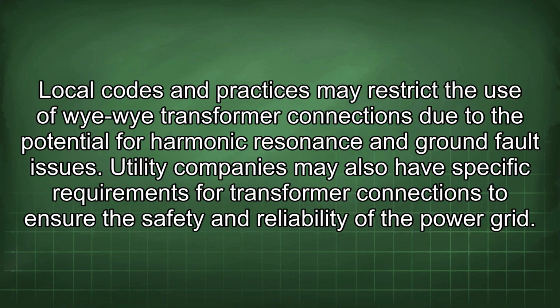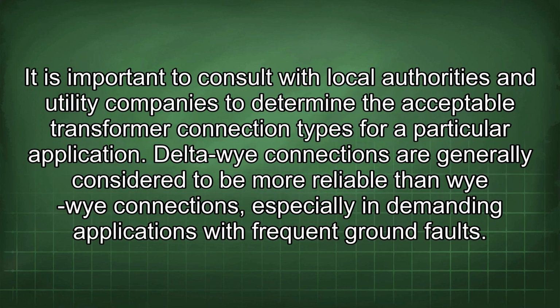Local codes and practices may restrict the use of Wye-Wye transformer connections due to the potential for harmonic resonance and ground fault issues. Utility companies may also have specific requirements for transformer connections to ensure the safety and reliability of the power grid. It is important to consult with local authorities and utility companies to determine the acceptable transformer connection types for a particular application.